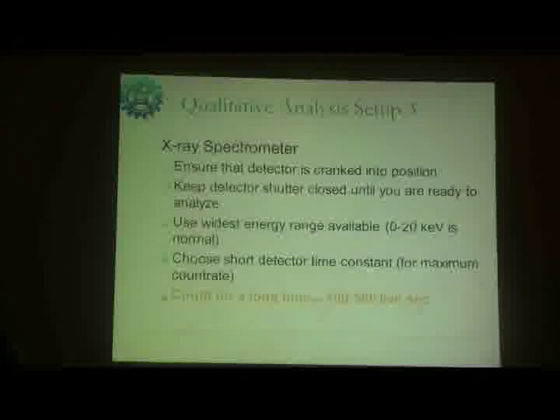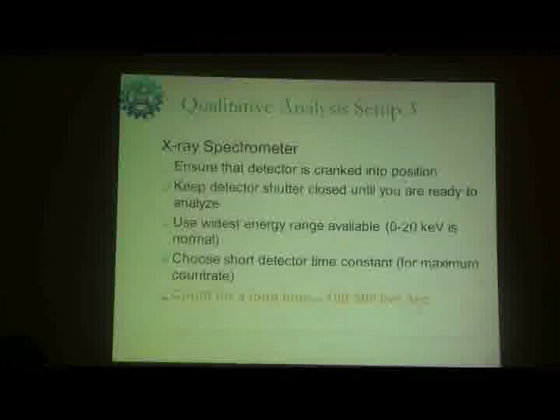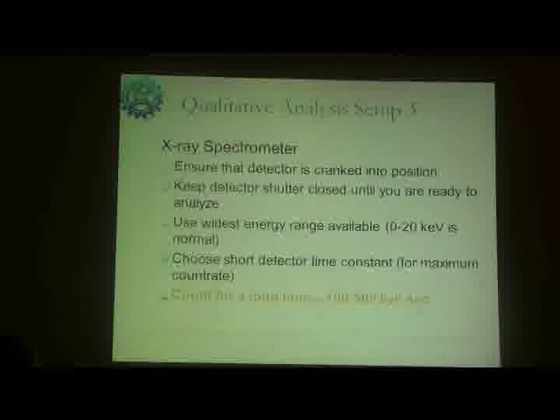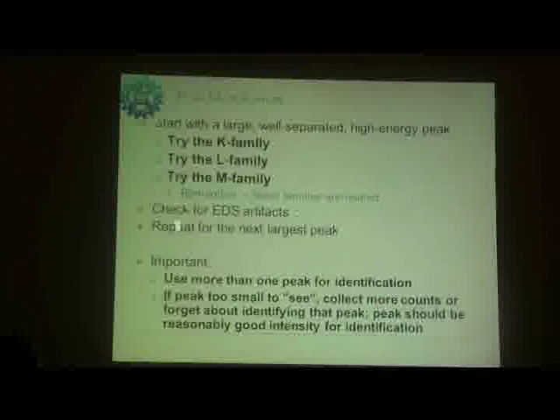So you can do the X-ray spectrometer also. Normally the X-ray detector is retractable. Retractable means the detector will be positioned whenever you want to use it. When you don't use it, the detector can be motorized, so you can retract it backward and position it in the same place. Whenever you want to use it, you bring it to the detector position and detect the EDS. So these are the detector conditions you have to set in the X-ray spectrometer.